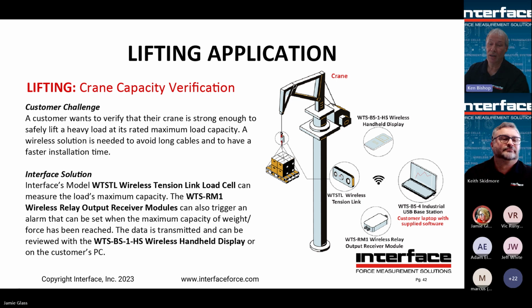That's going to provide them with relay outputs based on the readings that come from the tension link load cell, and set some alarms off, either a light bar maybe, or a horn. They also have a handheld base station, so they can monitor the load as it's lifted. And also what we call a BS4, which is a USB base station that comes with the supplied Log 100 software. So as they perform this verification process, they'll be able to log to the PC all that occurred during the test.